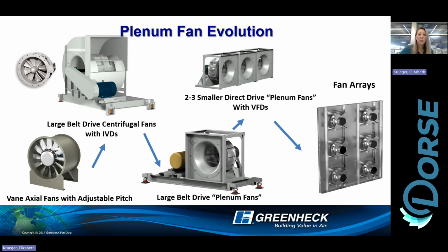Moved on to a little bit smaller footprint. So these are more traditional plenum fans. Again, it's basically moving air from one space to another. A plenum is a box that's pressurized, and that pressurized air will flow and can feed entire buildings, skyscrapers, that sort of thing. From the belt drive, we transition to direct drive fans. That's most likely what you'll see pictures of for retrofits nowadays for air handlers anyway. And now we've moved on to fan arrays, and so much more benefit and redundancy and efficiency is coming from all of this new technology associated with fan arrays.